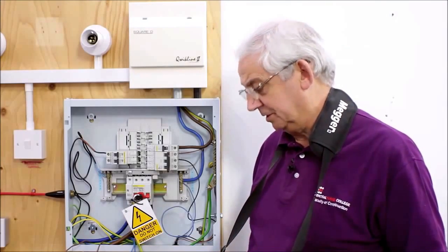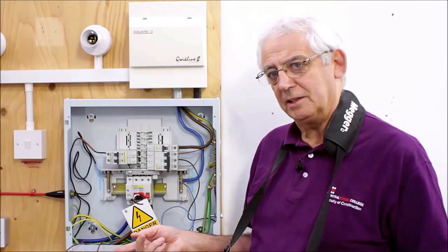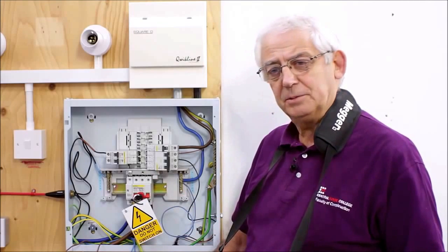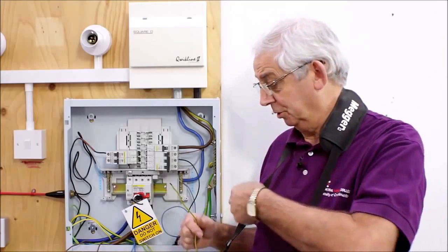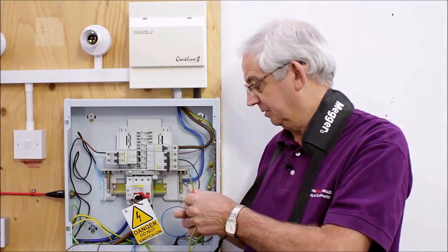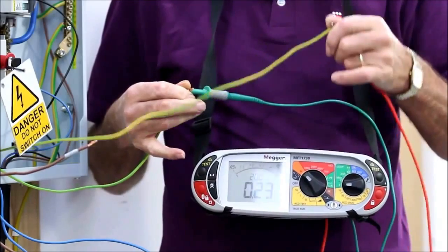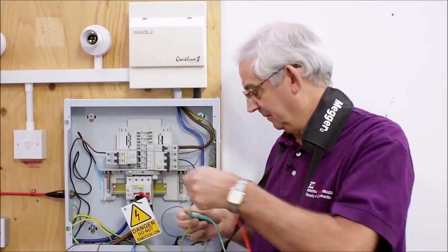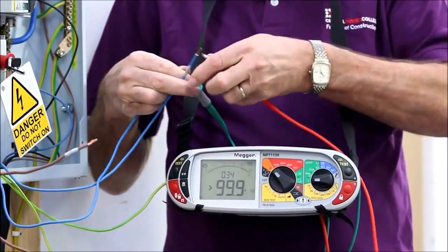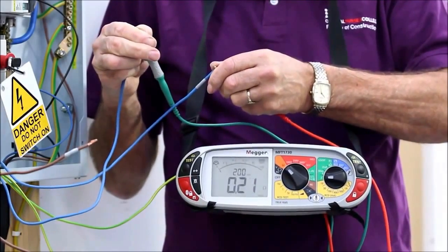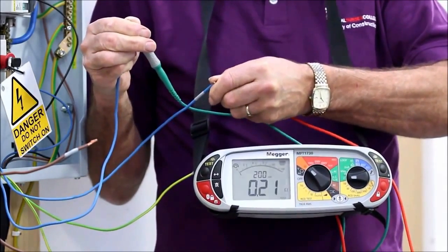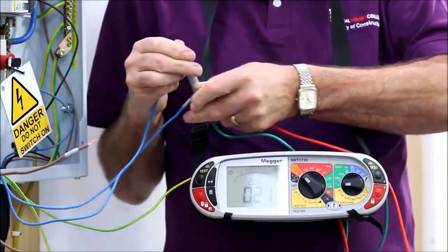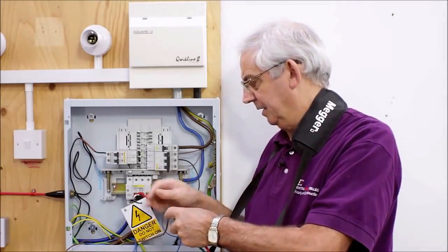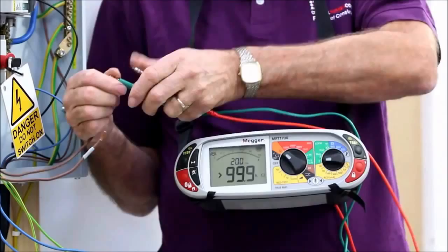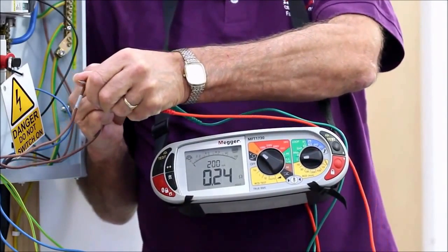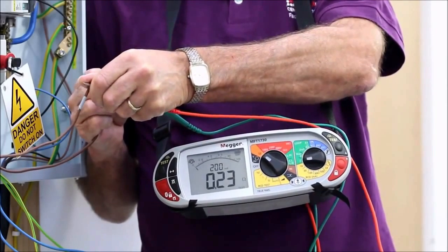I now need to measure the resistance end to end of each conductor. Because these are the same size conductors, they're all going, or should be, the same value of resistance. So I'll measure this, 0.23. Now I do the blues or the neutrals. It should be within 0.05 of 0.23, so that's close enough. And again, I now need to do the browns or the line conductors end to end. And the value should be very close to 0.23.